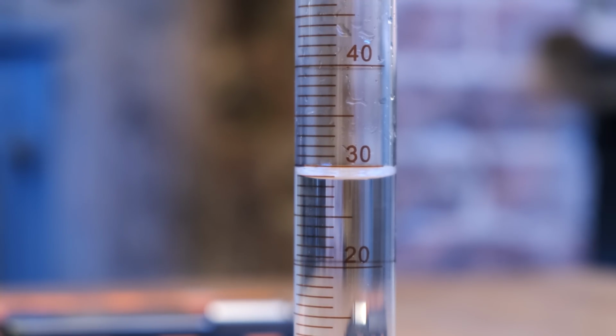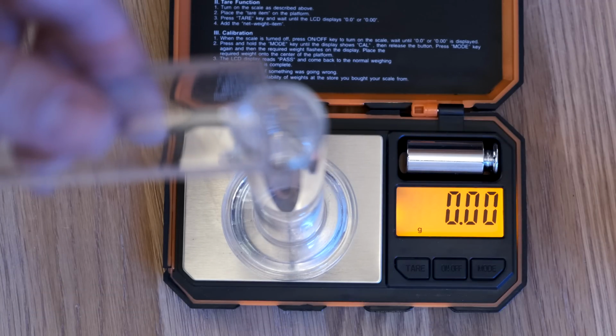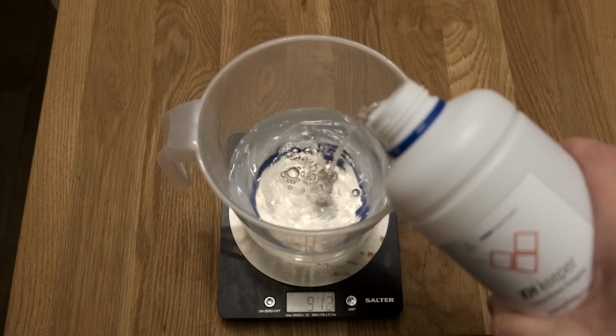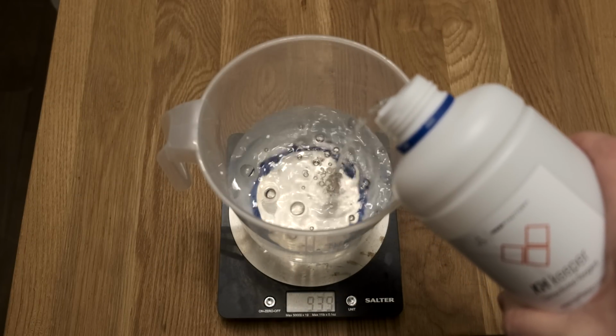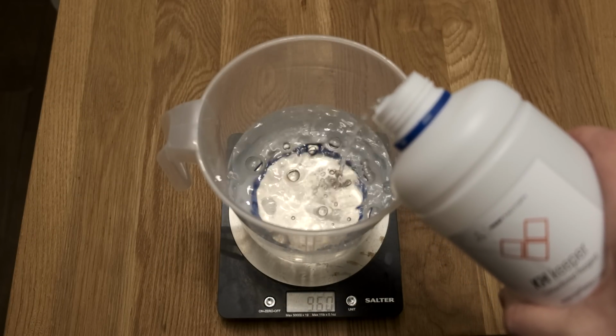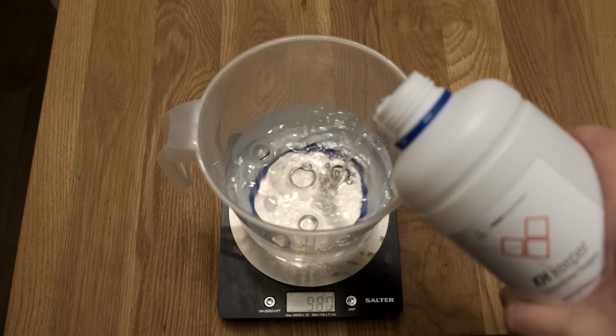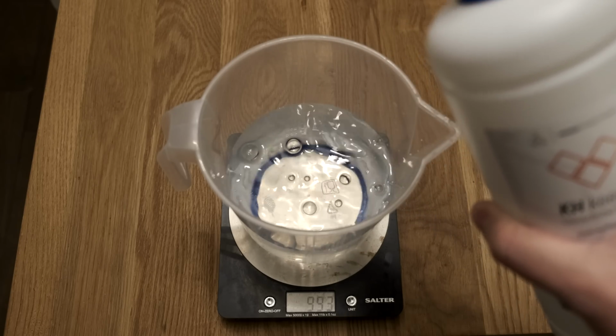I can never accurately read measuring cylinders, so instead I used a set of digital precision scales to calibrate the dosing heads. And because the reagent comes concentrated, I use a set of kitchen scales rather than a volumetric cylinder to measure out 100 millilitres of reagent and 900 millilitres of RO water. And I'll put links in the description to the scales I've used.